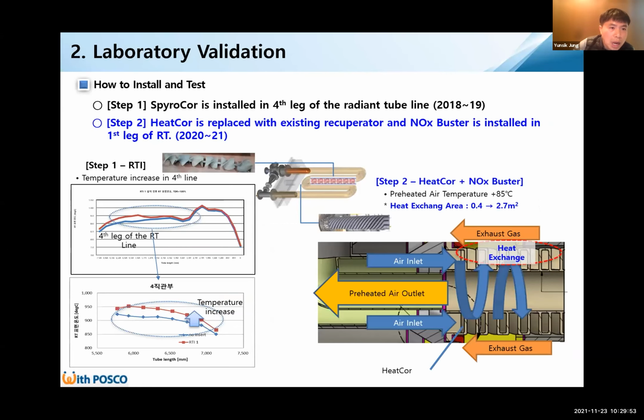I will explain how we installed and tested. In order to perform laboratory validation, we decided to proceed in two steps. Step 1, SpyroCor is installed in the fourth leg of the radiant tube line. Step 2, the existing recuperator is replaced with a HeatCor, and NOx Buster is installed in the first straight leg of the radiant tube.